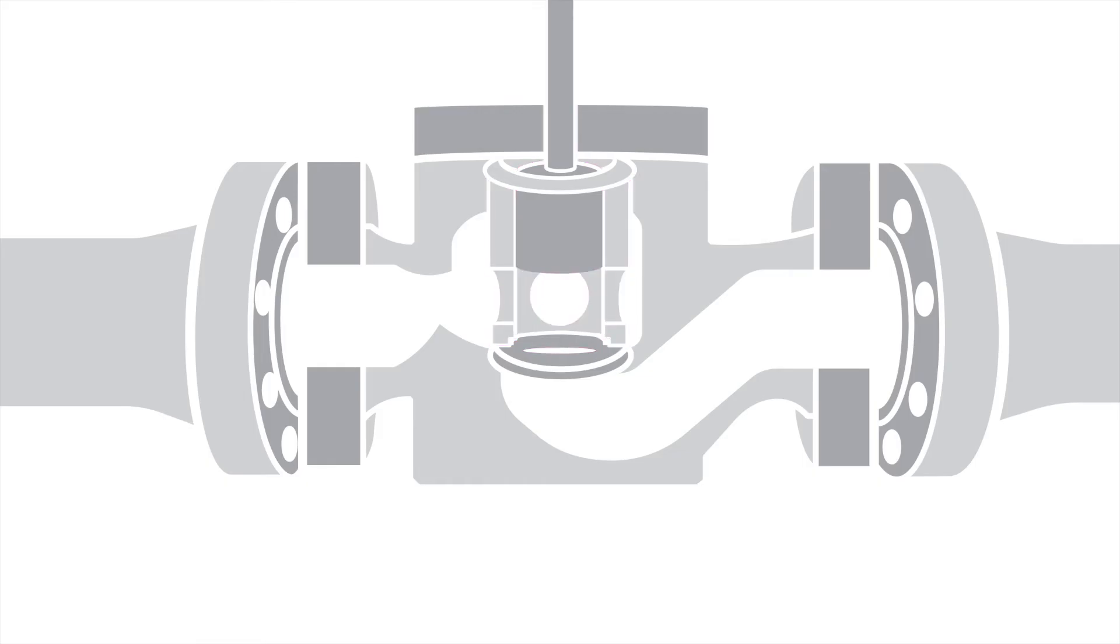Just like the doorway, there are different positions you can put the control valve in from closed to wide open, or anywhere in between. A control valve has a shutoff when the valve plug is on the seat. Then it throttles and goes to wide open. Basically, all we're doing is changing that flow area via movement of the trim.